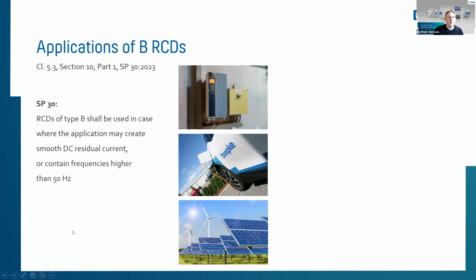Coming to type B, what are the applications for type B? In general, we can say all three-phase loads or three-phase applications where direct DC currents can occur would need a type B RCCB. This is described in a lot of standards, in the Indian standard as well as in the IEC standards, but a lot of markets are still at the moment not using it properly. So we have to educate people to use that kind of RCD type B in the application to be on the safe side.